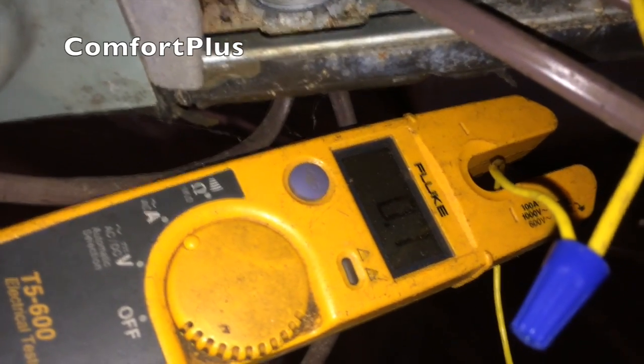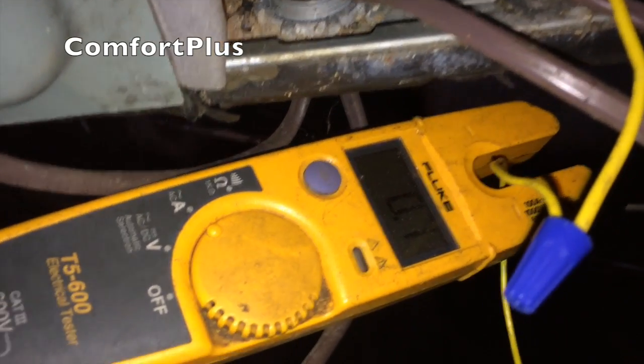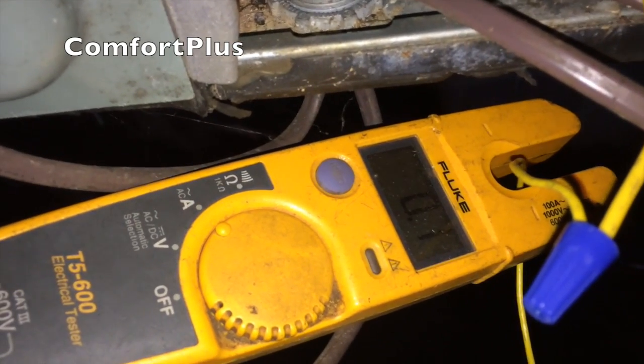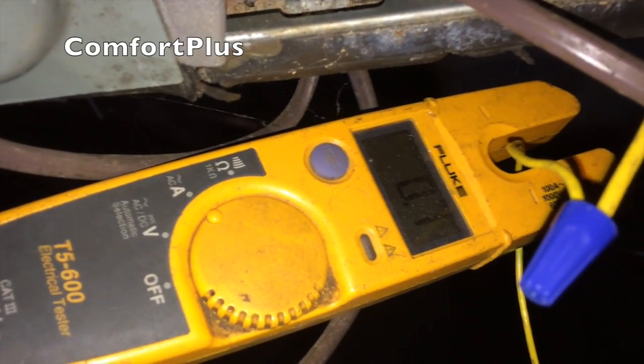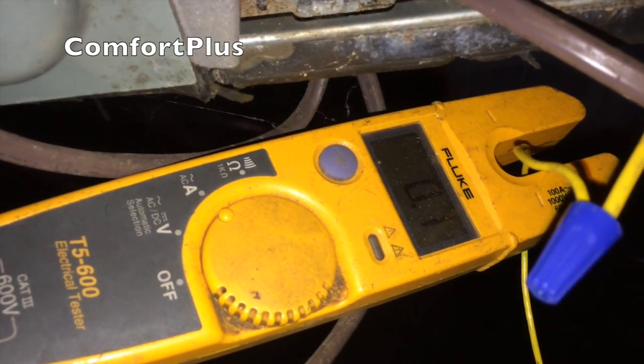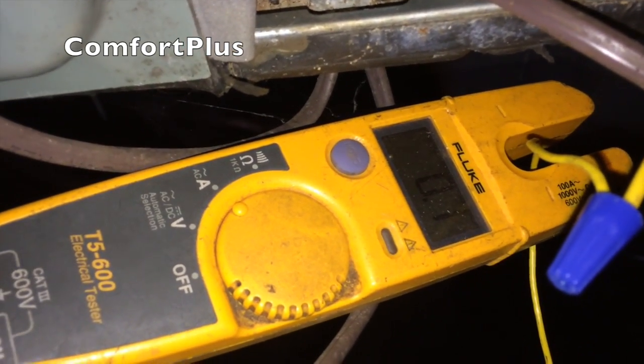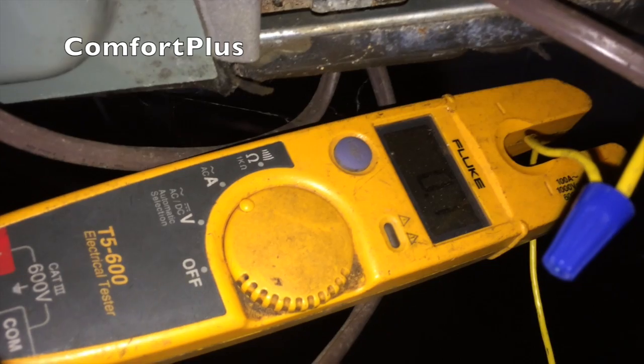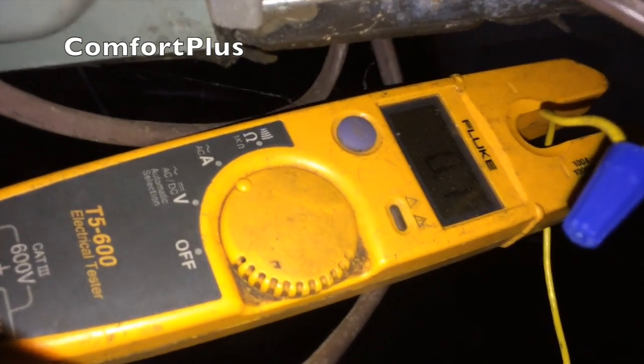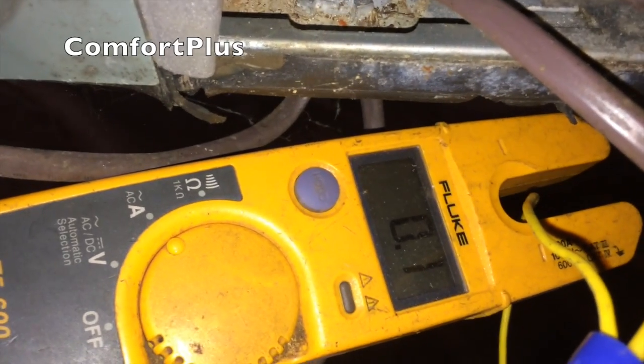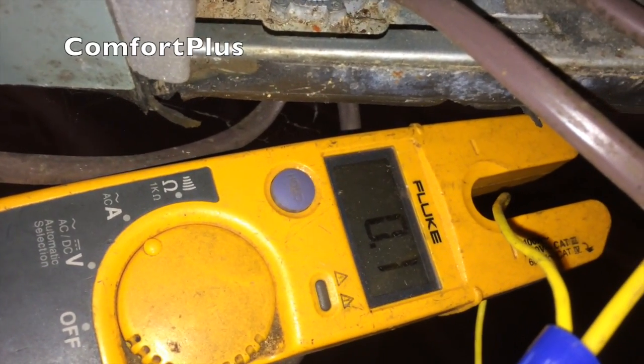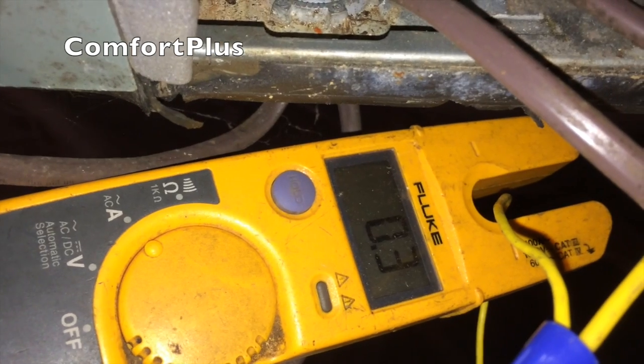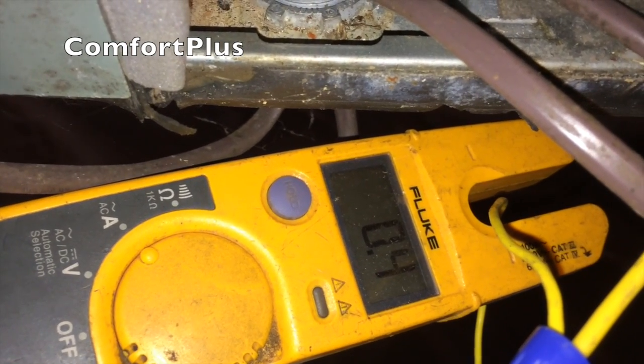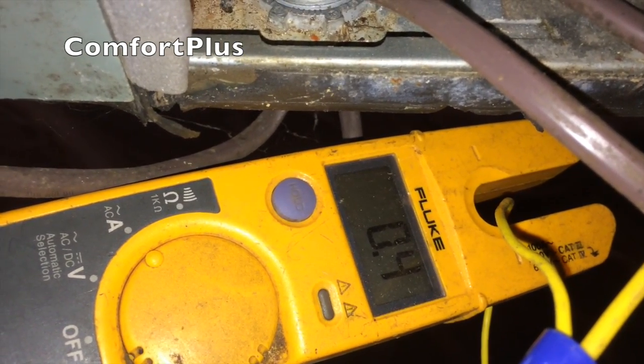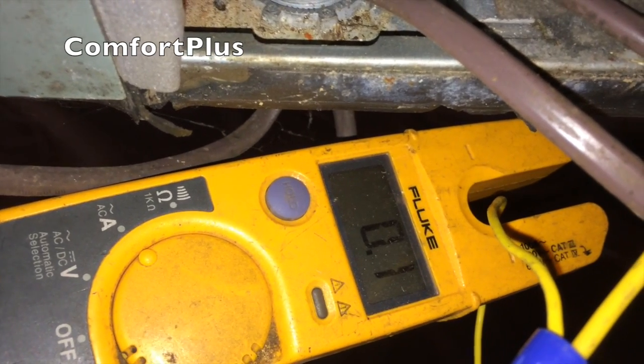Well guys, I looked at the board real careful, and there's no burnt places or anything on it. The blue just runs through a relay on the board and then goes over to the reversing valve. So I plugged it back up and came down here, and when I hooked the blues together now, see if I can get a good focus on this. When I hook the blues together now, I hear the valve engage outside. However, it doesn't pull the 11 amps any longer.